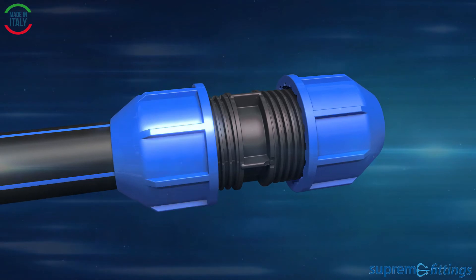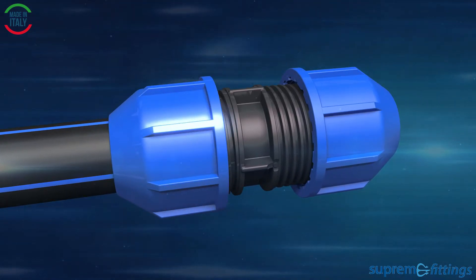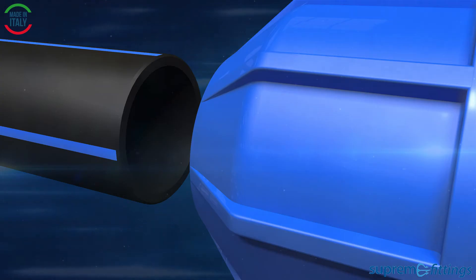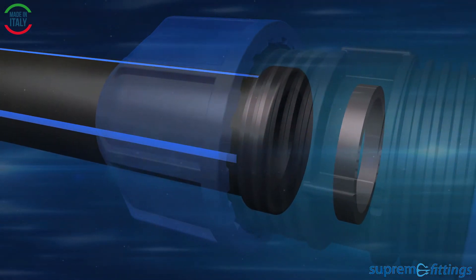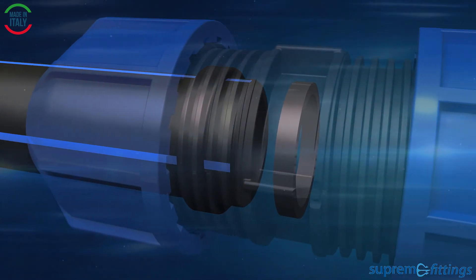The assembly goes very smoothly. The nut does not have to be removed from the coupling. Cut the pipe, chamfer the pipe and insert the pipe into the coupling up to the sealing ring. Continue to press till the stop ring.